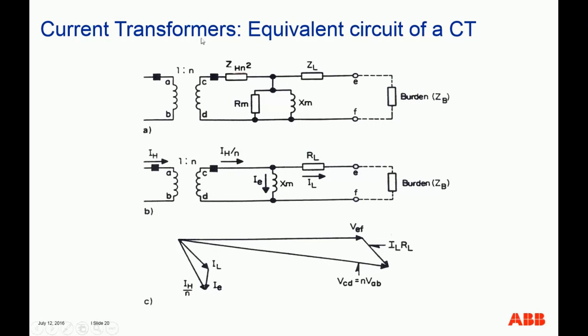First of all, the modeling. The current transformer is modeled as an ideal current source. So you would have a ratio current. Basically, it's the perfect replica of the primary current divided by the turns ratio of the transformer. Okay, and then you have your excitation branch, which can be represented by a reactance only. The resistance can be ignored, and then you have your CT lead or wire resistance, and your secondary CT winding resistance. Okay, and then you have your burden. The burden typically is your protective relay. For modern, low impedance protective relays, the burden is pretty low.